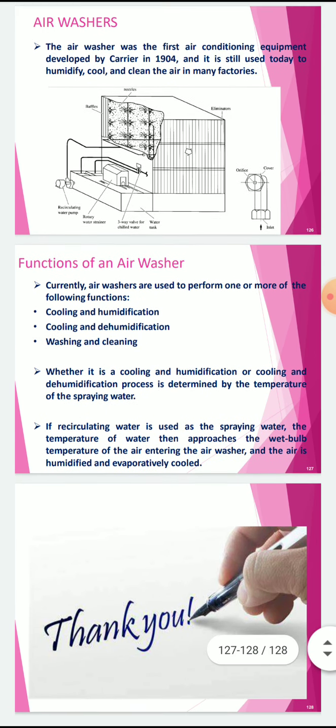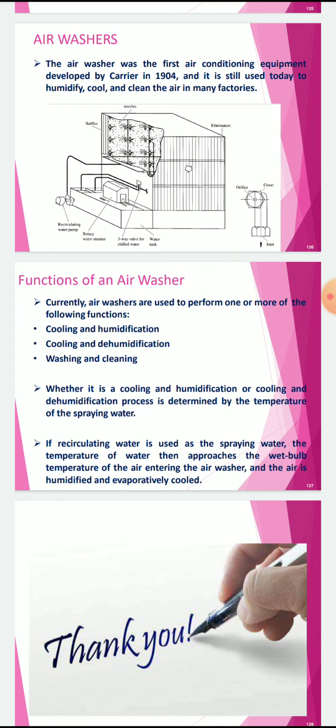Functions of air washers. Currently, air washers are used to perform one or more of the following functions: cooling and humidification, cooling and dehumidification, washing and cleaning. Whether it is cooling and humidification or cooling and dehumidification process is determined by the temperature of the spraying water.